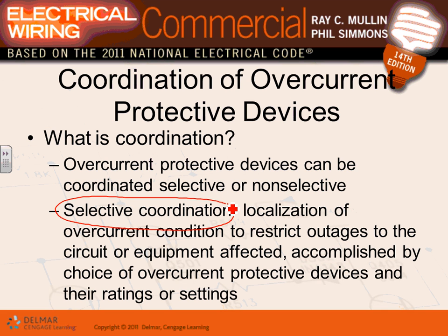Required in an NEC code book in emergency systems, legally required standby systems. For every single engineered project, we run a short circuit calculation and overcurrent protection coordination studies to make sure we have selectivity.